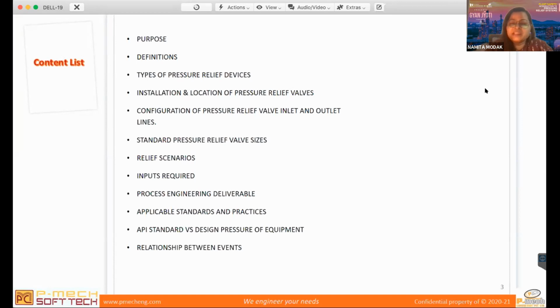Then relieving pressure. Basically, relieving pressure is the maximum pressure at which it can depressurize your system. Set pressure is your design pressure, but if you refer to API 521, you will see different types of PSVs are given: conventional, pilot operated, balanced bellows. They have a range based on single PSVs, multiple PSVs, and whether the PSV you're sizing is for a fire case or non-fire case. The percent overpressure is mentioned in API 521. So let's say I am designing for a non-fire case.